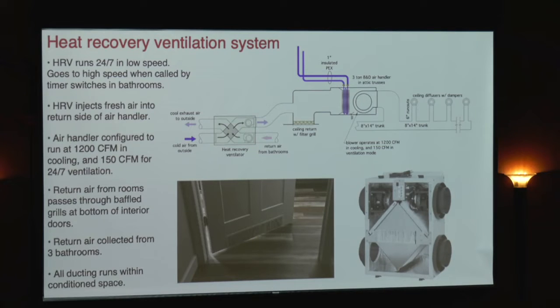So we found a company. It's actually up in New Hampshire. It's called Tamarack Technologies. Anybody ever heard of them? Tamarack Technologies. They make these grills that can be cut into the bottom of a door, and they are designed to suppress acoustic transfer as well as line of sight transfer, light transfer. They have baffles in there, but they allow air to come through, and you get a pretty significant return airflow. In fact, Allison Bales did some testing on these things with manometers, and he was demonstrating they work pretty well.